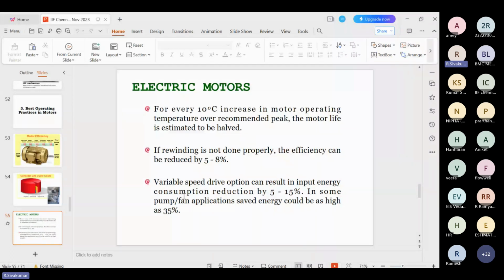One classical example is the air compressor. Wherever the air compressor loading is less than 60% or 70%, you may go with the VFD, so that 30% of the unloading power can be saved. At least 20% of the unloading cost can be saved. So the payback is also very attractive for VFDs.